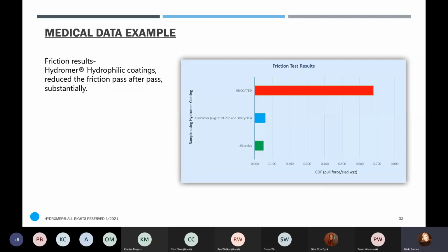Getting into the friction results, which is really important with 99% of our customers, obviously. We pride ourselves on this, again, going back to the UV curing and our thermal curing and our hydrophilic coatings that we've had for 40 years. You'll get this graph along with a couple other pieces of information, again, with each lot. And what this graph is showing you is the uncoated being the red bar compared to the blue and green, which is the coated product at 1 to 3 cycles, and then 25 cycles on our friction test, showing the coefficient of friction.